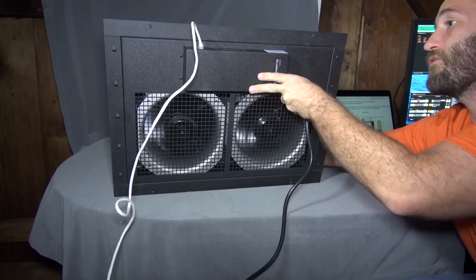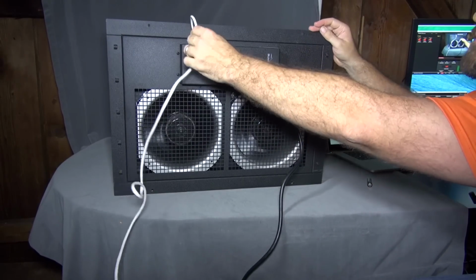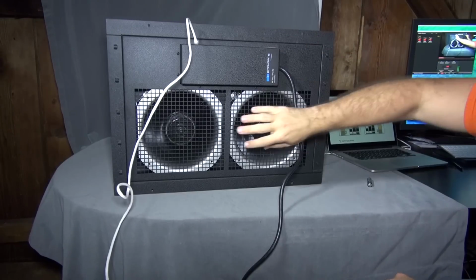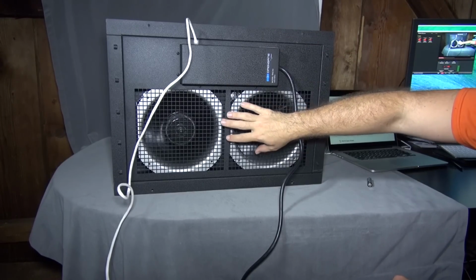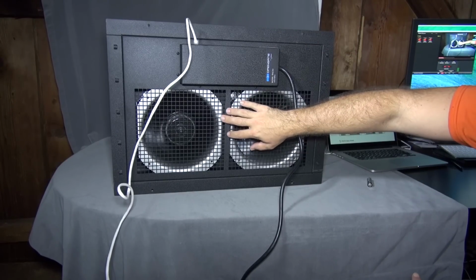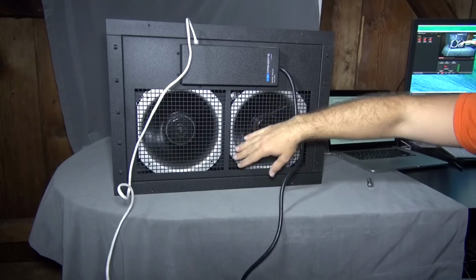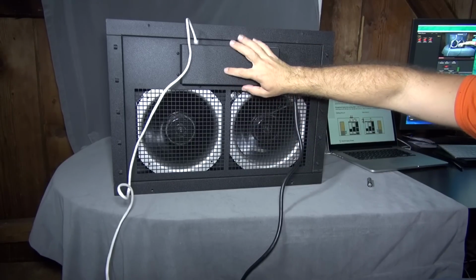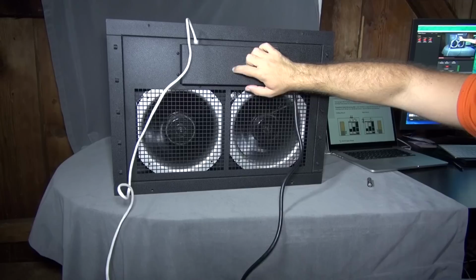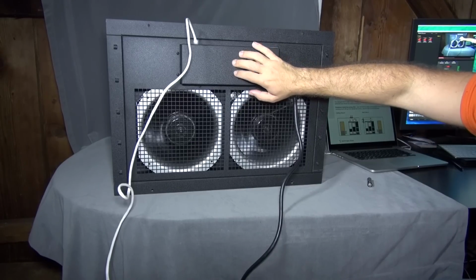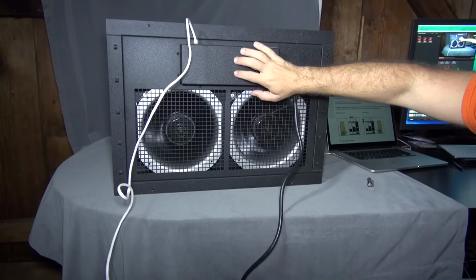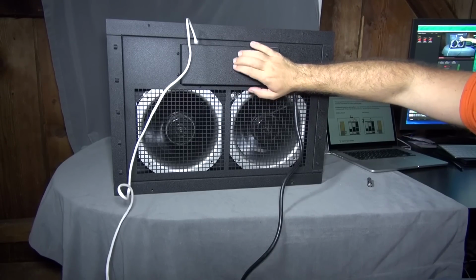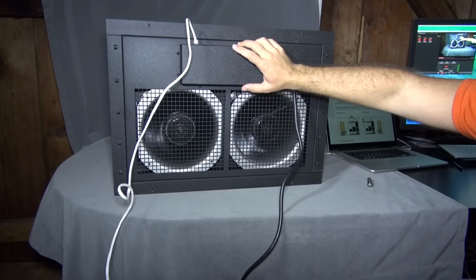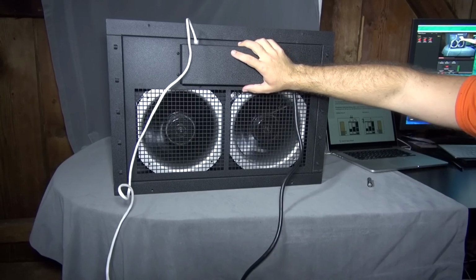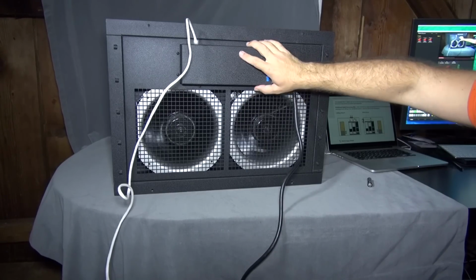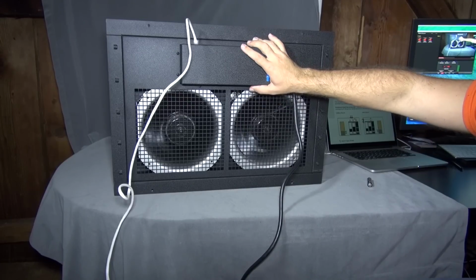Beyond configuring the fan system, what's nice about having this plugged into the network is that it has temperature sensors to tell it when to turn on and off, or speed up and slow down, and it can also send out alerts. It can send email alerts when certain conditions are triggered, and it can send SNMP alerts—if you have a simple network management protocol system, this can send information to that system so you know what's going on.